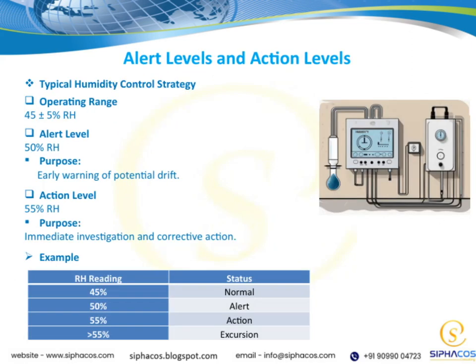Let's talk about humidity control and how we keep things on track. We aim to stay around 45% relative humidity, plus or minus 5%. When it hits 50%, that's our alert level, a heads up that something might be drifting. If it reaches 55%, that's action time. We investigate right away and take corrective steps. Anything above 55% is considered an excursion, meaning we've gone beyond normal limits and need to respond quickly. This table lays out those thresholds clearly.